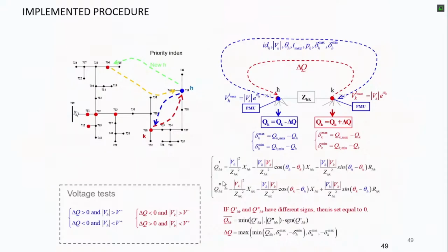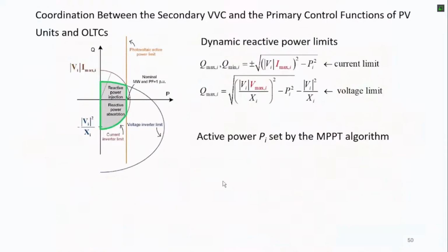So there is also a coordination between this algorithm and the local controller. We can say that this mechanism acts as a secondary voltage control, but the primary voltage control is there. I mean, there is the controller of the photovoltaic units that controls the voltage in the bus bar, taking into account the limitations. These are the typical limitations of the maximum current in the converters and the maximum voltage in the DC bus inside the inverter.